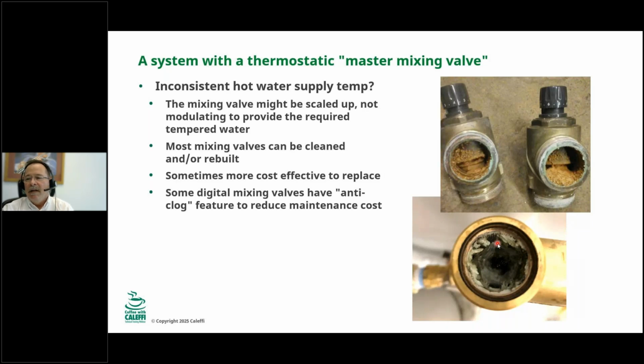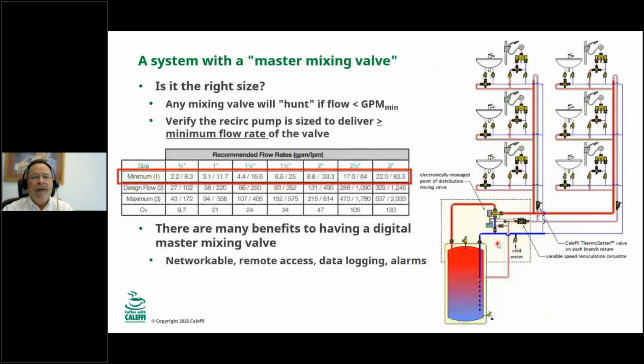All right, another big thing that we hear about in our technical support center is hunting. The valve is hunting. It's cold, it's hot, it's cold, it's hot. The valve has to be the right size. The master mixing valve cannot be oversized. If you put a valve in that's too big, then it's trying to control near closed all the time. It will hunt. Any control valve will, whether it's a plumbing control valve or an HVAC control valve. It has to be sized right.